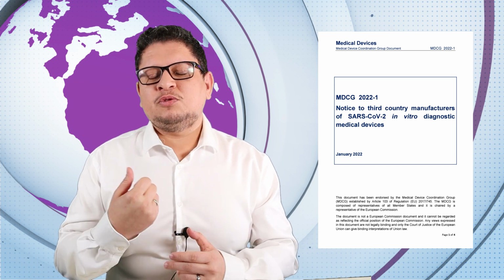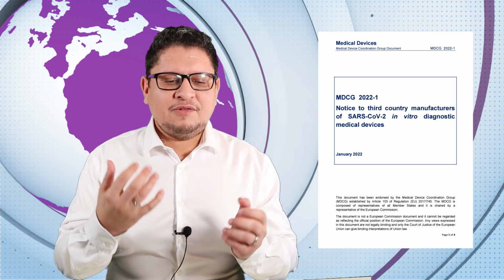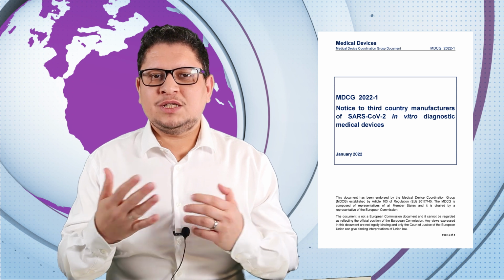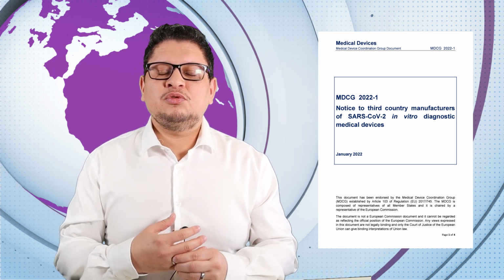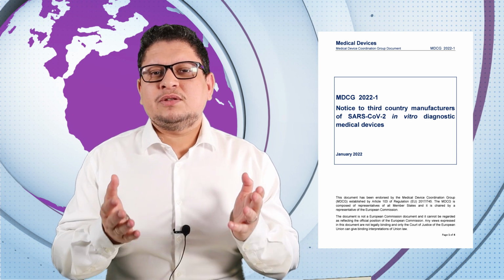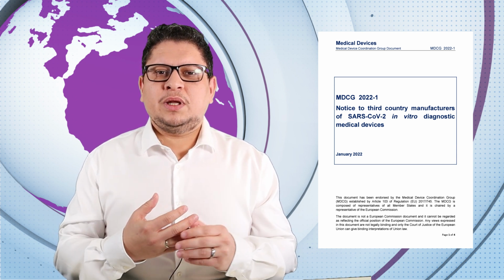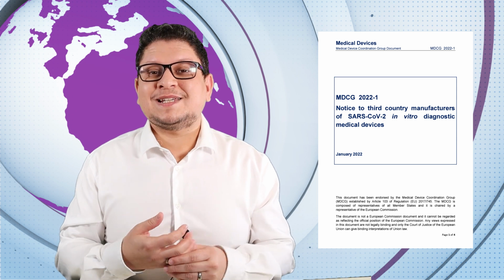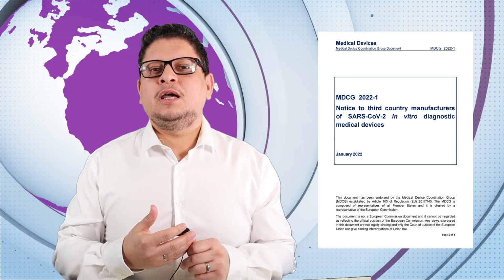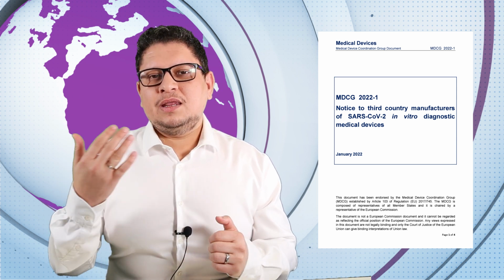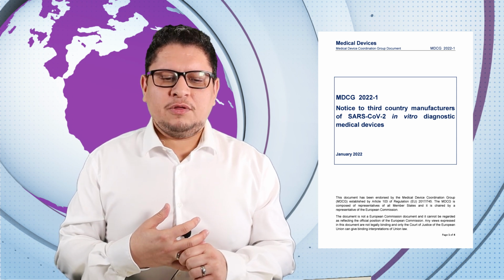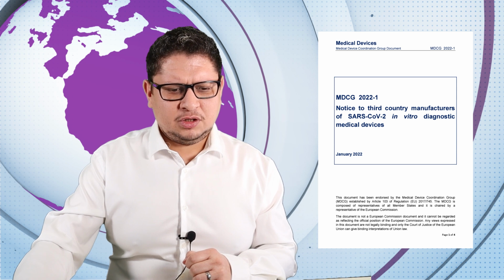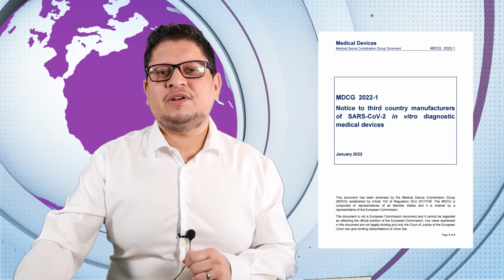The last one is about the transition period. We have Article 110, which talks about the transition period. As we said before, there will be some changes for some products. COVID-19 in vitro diagnostic products are considered class D products, the highest risk products, and they will have to be compliant by the 26th of May 2024, if I remember, or 2025, I can't remember, just a second.